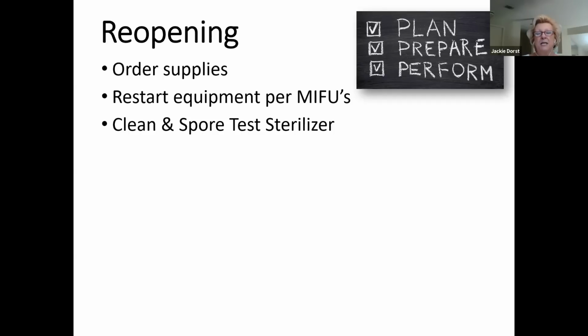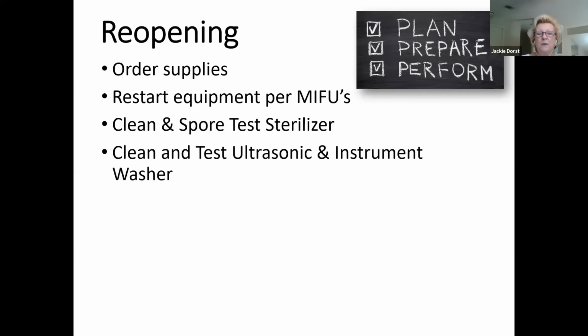If it's been shut down for an extended period of time, the CDC's current recommendation is that you run 3 spore tests and get back-to-back results, to make sure there wasn't an error or oversight before you implement use again.